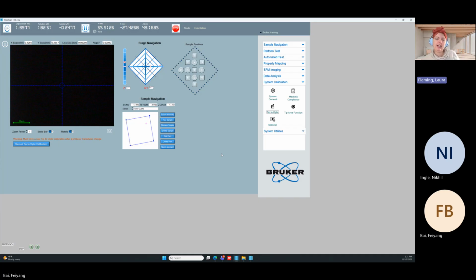Okay, so what I'm trying to get at here is that when you're setting up the instrument for scratch testing, the question is, is my tip area function accurate? The last one that we have to answer before we can begin testing on our samples. It's a little bit tricky when it comes to scratch because the answer is it doesn't matter. I'm not getting hardness and modulus results. So we can go ahead and say, okay, that's good enough.